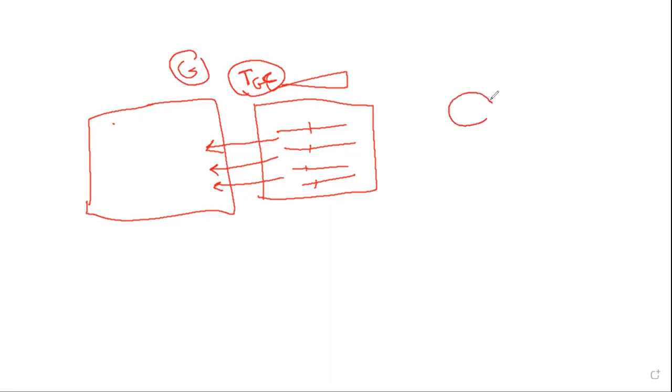But what about the knob here? Here the knob, when you move it this way or the other, it controls the whole of the image as a whole. But the TGC, every little slider controls one sector of the image. This allows more control over each part of the image. So this is the difference between the TGC and the gain.